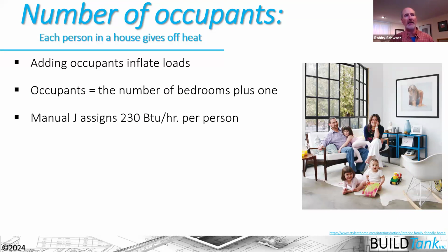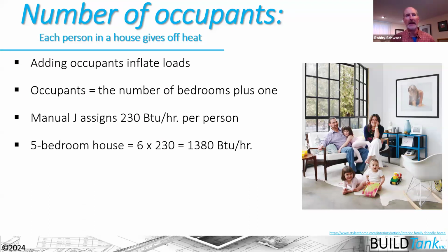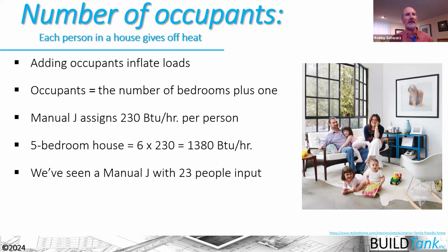So Manual J assigns 230 BTUs per hour per person in that house. So for a 5-bedroom house, that would be a total of 1,380 BTU per hour that we need to take into account. Now, that would be taken into account more in the cooling season because we're going to need to be able to cool that 1,380 BTU per hour. In the heating season, we're actually helping to heat our house in essence. Not very much, but we are helping it. So it's taken into account differently in the cooling season and the heating season.